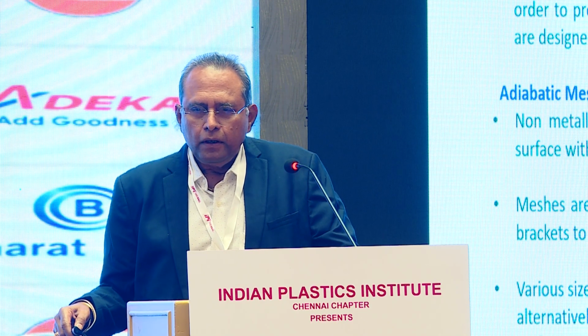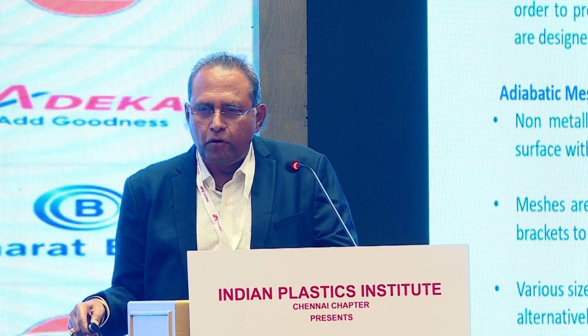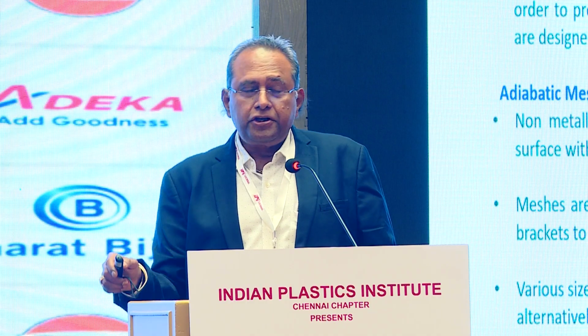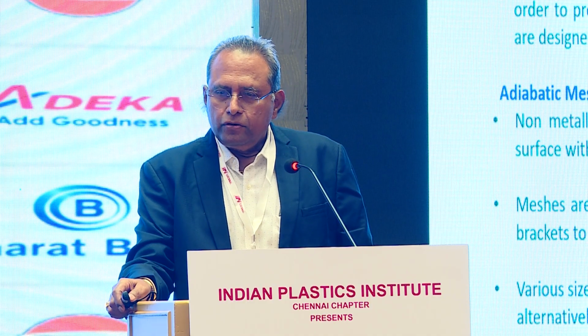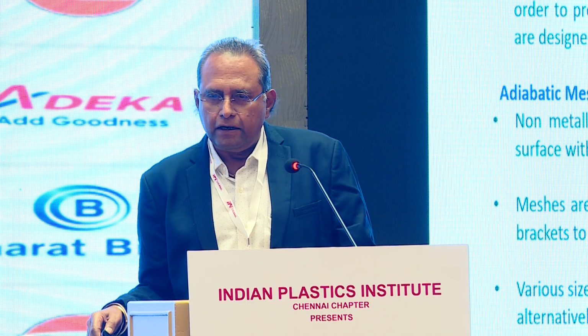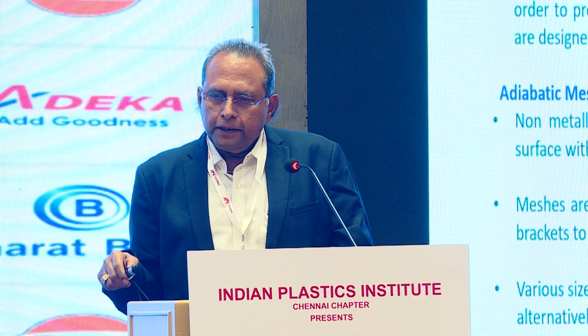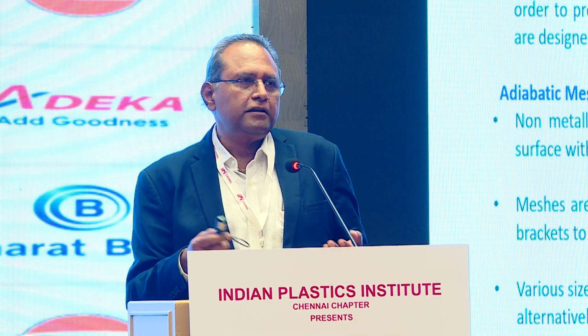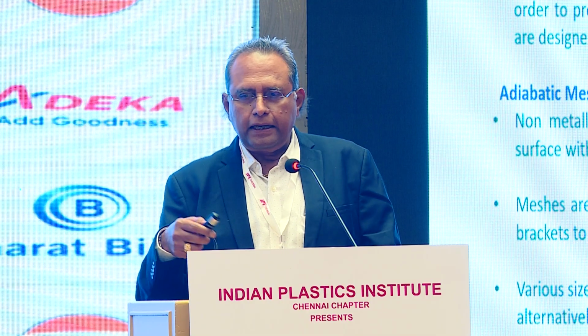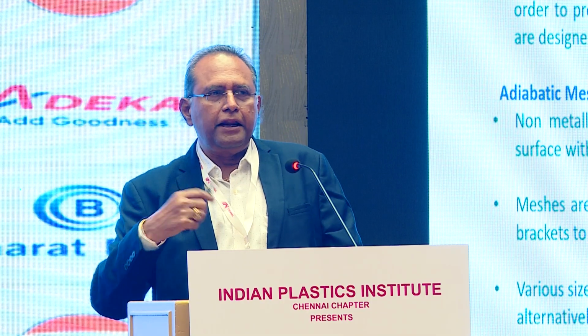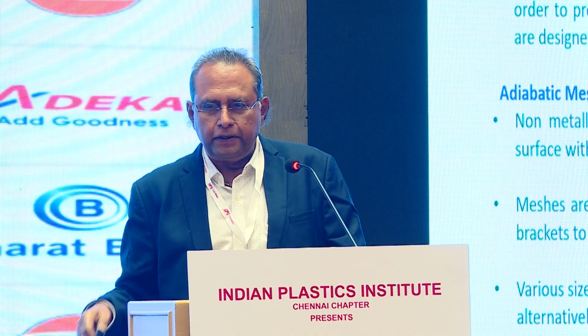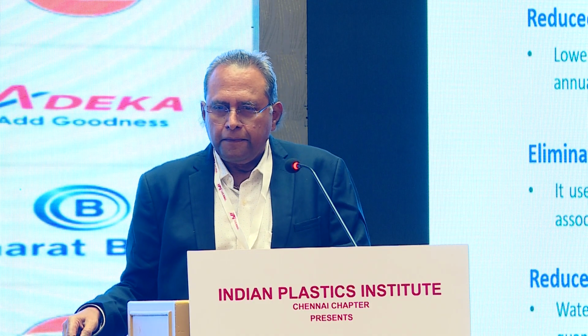So hot air is going and a small quantity of water is evaporated. Here there is a water loss, which will be partial when compared to the normal cooling tower evaporation. These non-metallic pads provide an efficient coverage area, a mesh in front of the heat rejection area. The fixing brackets and other options are available. The mesh pads are available in modules, so they can be replaced or serviced. You can replace parts of the radiator.